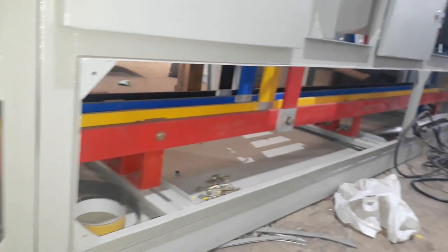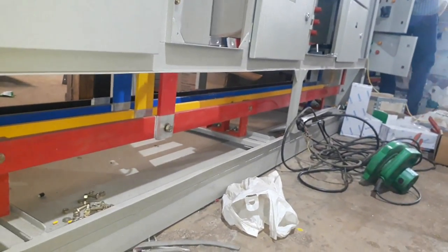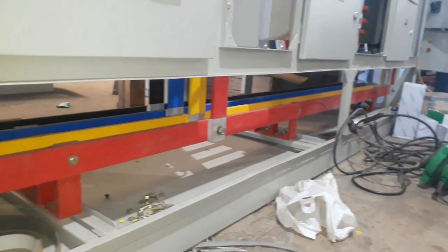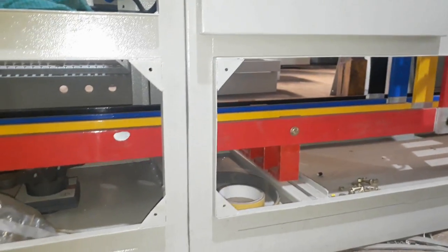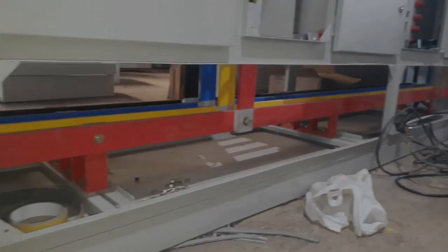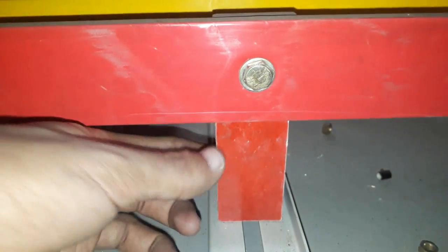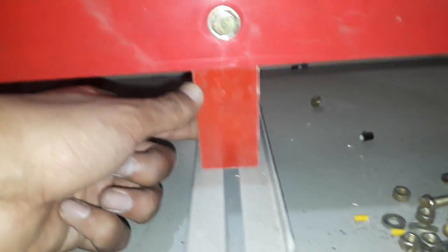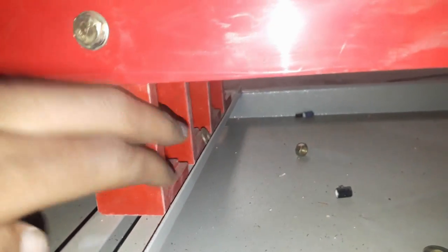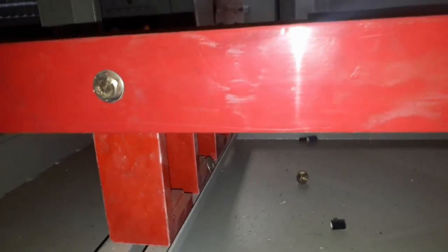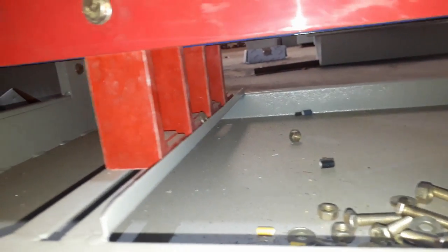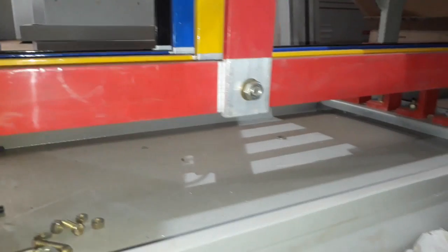Here you can see the bus bar chamber is at the bottom of the panel. In the previous panel videos, the bus bar chamber was at the top of the panel. Here you can see these are the insulators to prevent leakage of current to the body of this panel. So we are using insulators between the bus bars and the panel body. There are more bus bars and more insulators here, as you can see.